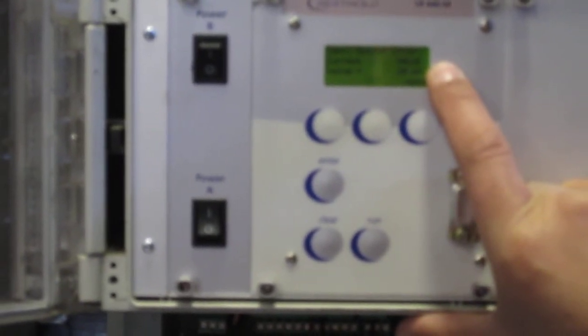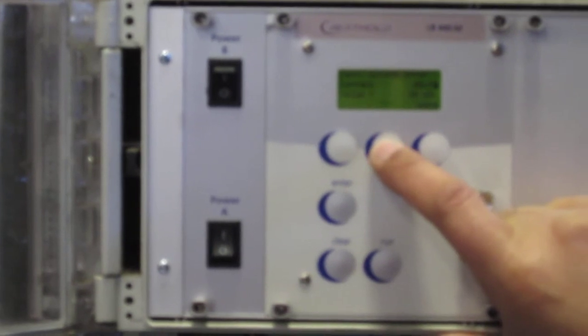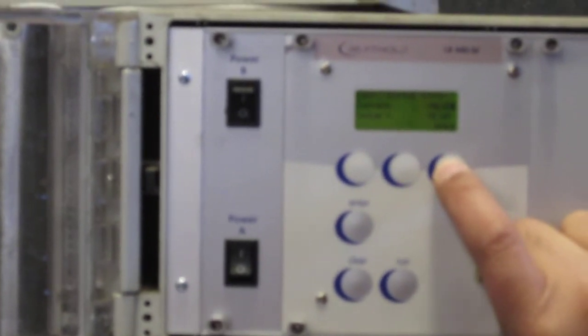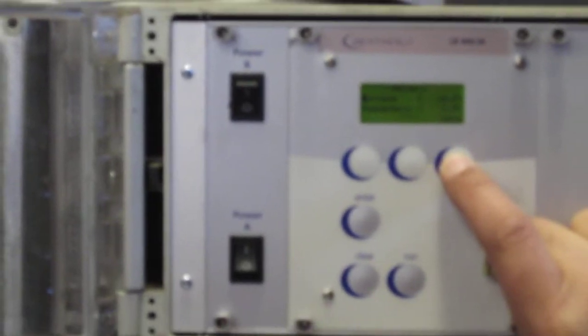And there's where we talked about the output error. You get a value, and that's what we set it to. You can't set it to hold. We wanted a value, and you're going to have a value of 20 milliamps, so that you'll know there's some type of error. You know your vessel's not full, which is what 20 milliamps will report to you, and then as soon as the error goes away, it's going to clear and start running again. So if there's an error, it's going to go right to 100%. It'll show you 100% out, but as soon as that error goes away, it'll clear.